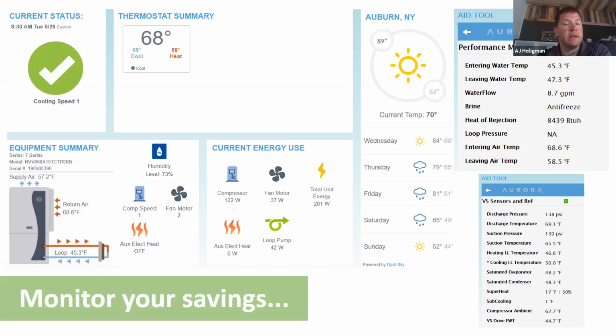The advantage of that is, for example, people just switched to air conditioning this weekend, and we had a lot of folks with clogged condensates. Instead of sending a tech out on overtime on the holiday, we can walk people through how to unclog their condensate - maybe they have a dirty filter, debris stuck in the drain pan, or the pump has become clogged with debris or algae. The alarm is detailed enough to tell us what it is, so we can decide whether to send somebody or let the homeowner diagnose it themselves to save money. Very few of these come in, but we did get some over the weekend because of cooling for the first time, or things like drywall dust.